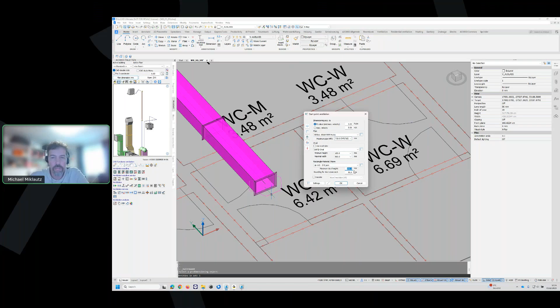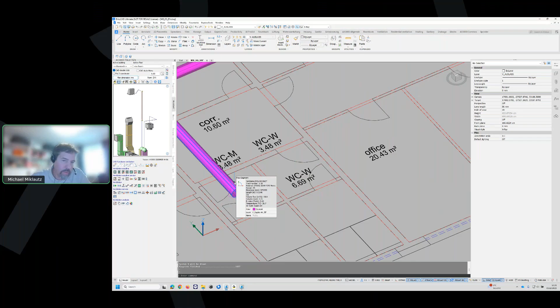So I can switch it to 0 maybe. Then there's no limitation for the height. That means you always get a round shaped duct. Let's say calculate, confirm. Okay, then you get a different result. It's not a square duct, it's a round one, because we said you are allowed to use up to 710 millimeter. At this point, we are using 355. Depending on this, it was a round shaped duct.